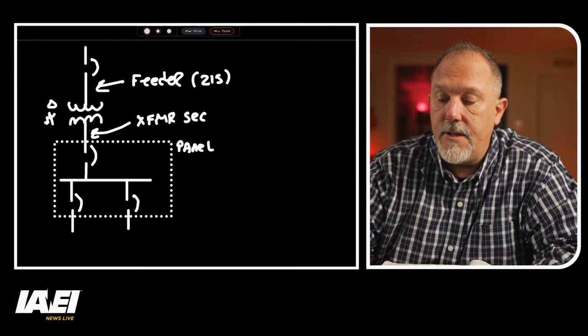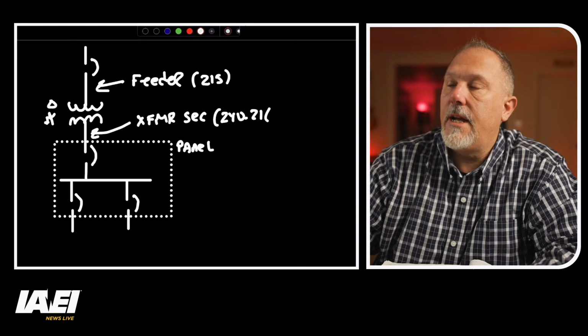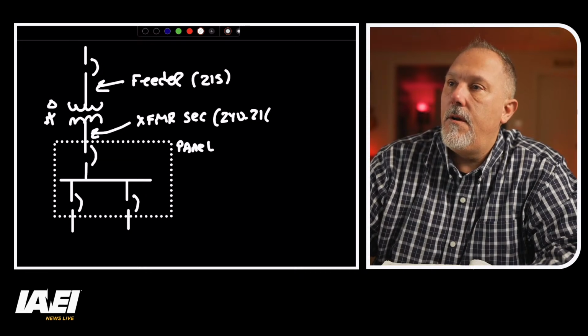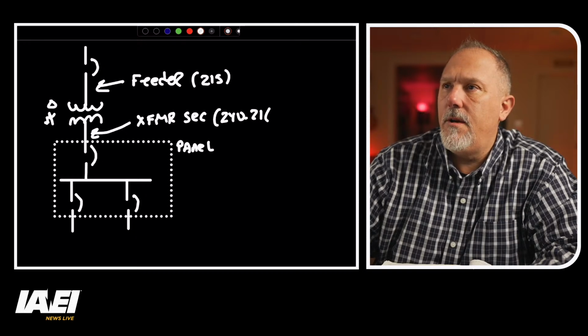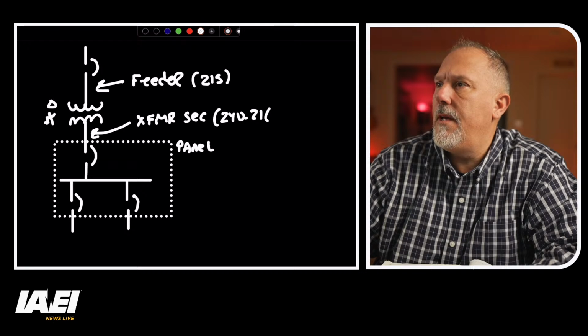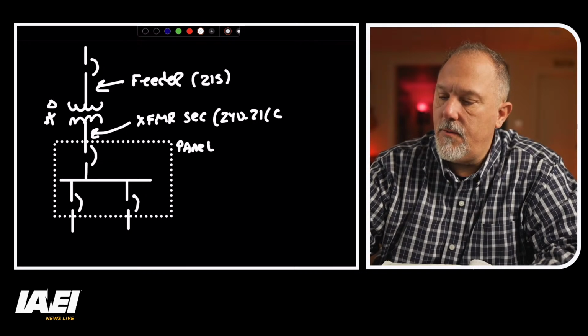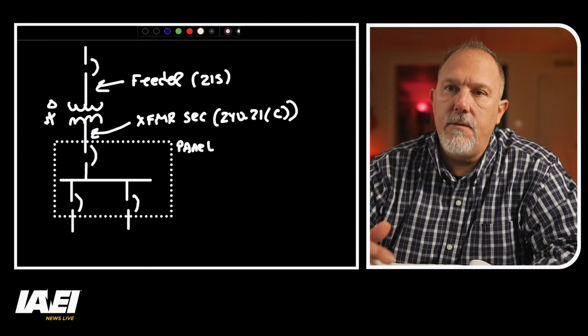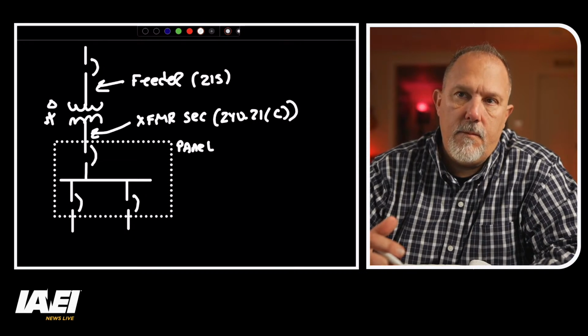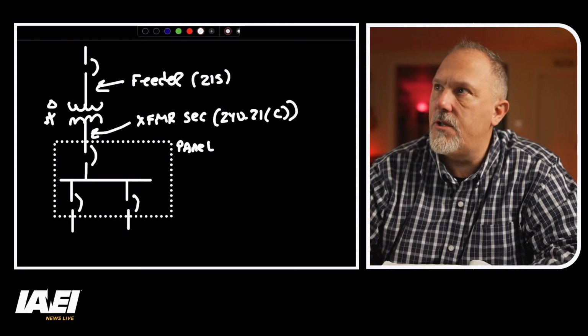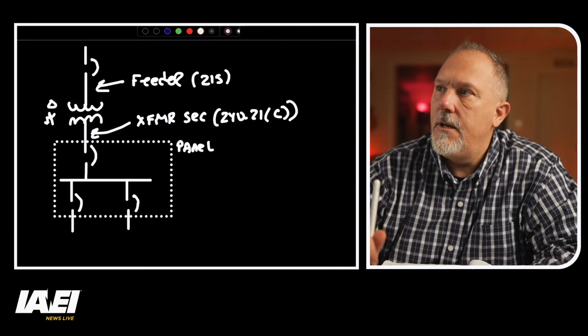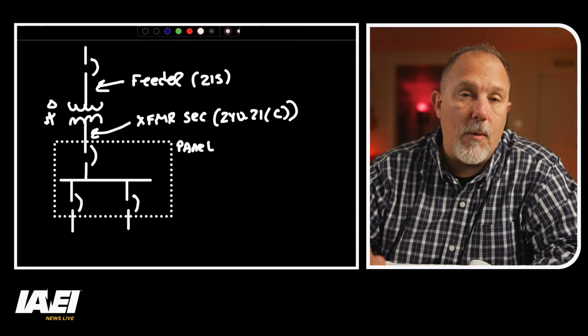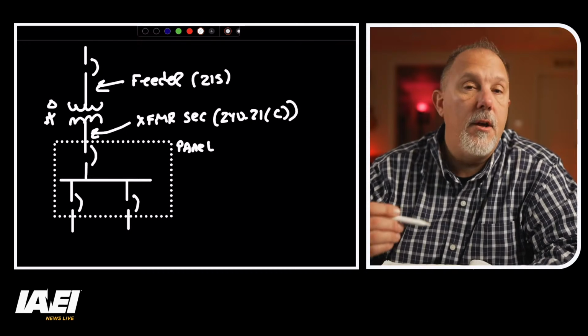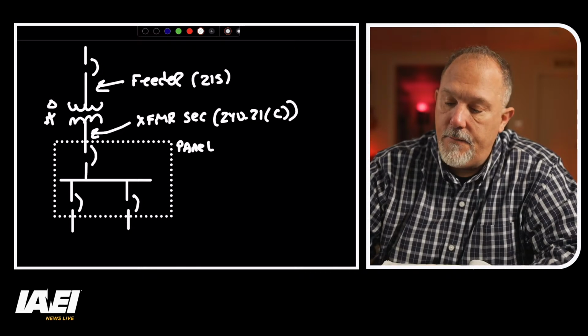This transformer secondary is going to be a 240.21. What's the section? 240. I hope I got the right one. 21. Yep. 240.21. Is it? It's not B. It's C. 240.21 Charlie. Okay, so that's the rules in 240.21C, which covers transformer secondary conductors. For a delta Y ground transformer, those conductors are not protected by the primary overcurrent device.